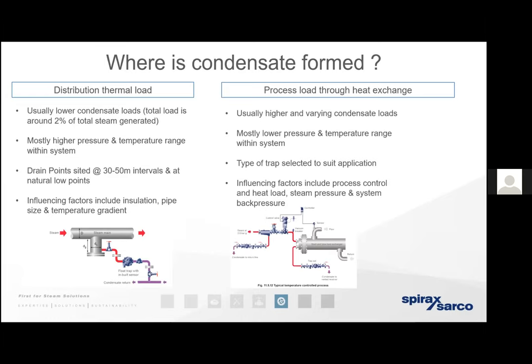We can refer to that as a distribution loss or heat loss. This helps us size steam trap capacity and determine how many traps are needed and how far apart to locate them. That 2% rule of thumb applies to the running load — when the network is already hot and operational for a number of hours. But after a weekend shutdown, starting from cold on a Monday morning, the infrastructure is also cold. We expect a far greater mass of steam to condense before the process gets up to temperature, so we always double that 2% to 4% to allow for the warming-up load.